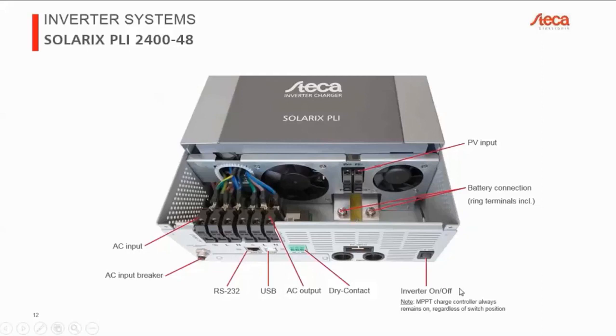Then we have the inverter on-off switch. Now, this switch is only the inverter portion. So basically, let's go back to our example of a weekend home, or any site where you only need the inverter periodically while you're there. You can simply switch the inverter off with a switch, but the charge controller will still continue to run. The switch is only switching the inverter on and off. The actual PV charging will continue to run regardless of the setting. What will happen is that during the night, the inverter will be completely off, the display will be off, everything will be off to conserve energy.